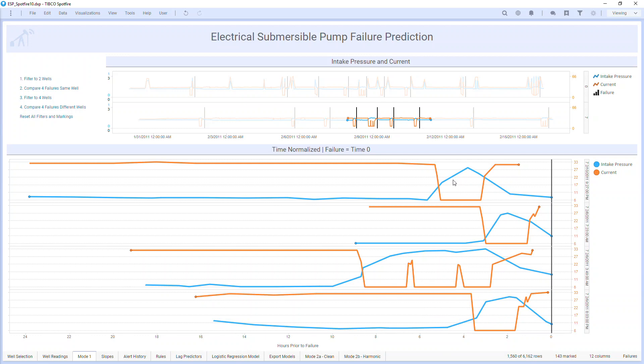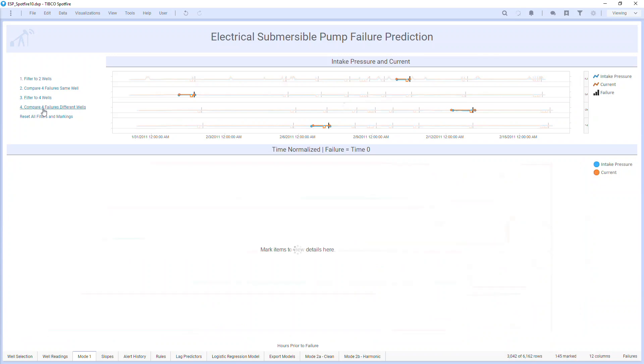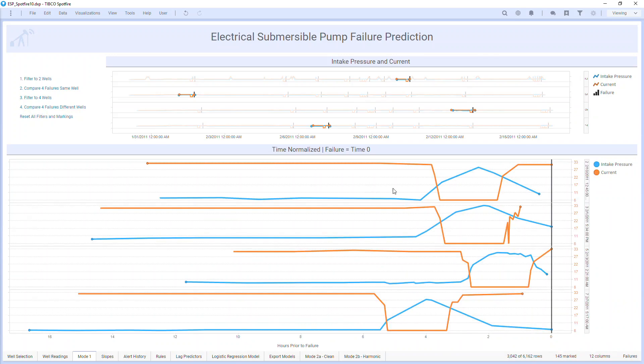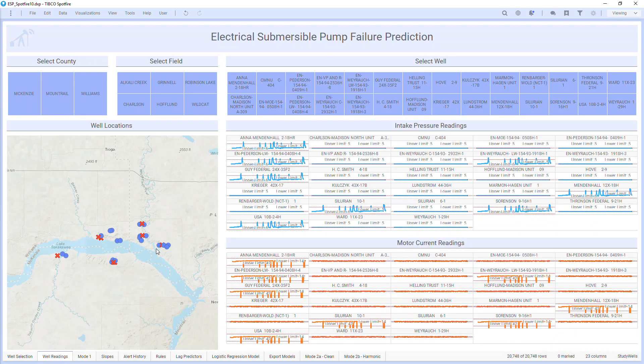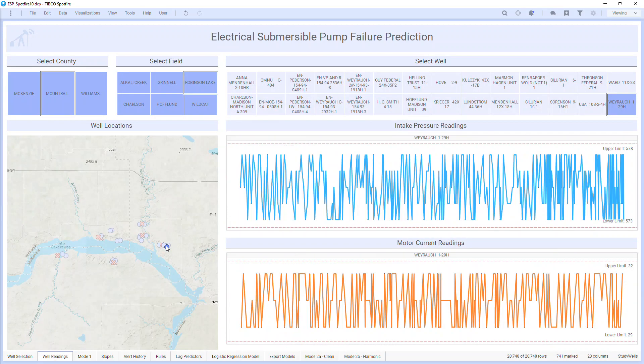This could be due to gas buildup or various other issues in the well. I'll expand this by looking at four different failures, each spread across four wells. I see the same pattern in these signals, indicating that this is a pretty consistent signature for all failures I want to start monitoring. However, when I go back and look at all my wells, I see even in good wells, pressure and current signals have noise and bounce around. So simply monitoring for inverse relationships of the two signals is not enough on its own — I'll get all sorts of false positives.